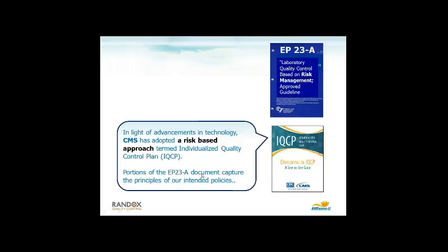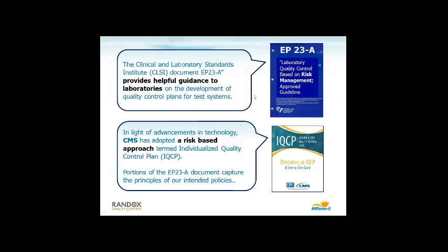Portions of the EP-23A document capture the principles of what they want to do. This EP-23A provides guidance on how to meet these regulations. It also provides guidance on how to manage risk in general in labs. You must do IQCP, you should do risk management.